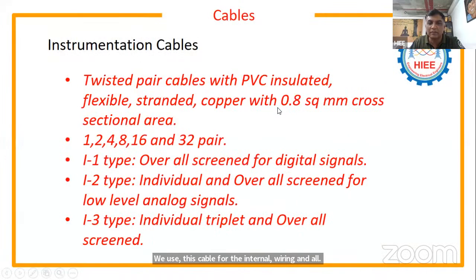Instrumentation cables we already mentioned. I told you instrumentation cables are used only for the PLC and the SCADA applications. Your instrumentation cables are also PVC insulated, and mostly the cross-sectional area of the conductor is 0.8 square mm. And instrumentation cables are available as 1 pair, 2 pair, 4, 6, 8, and 32 pair. You have different types of instrumentation cables.